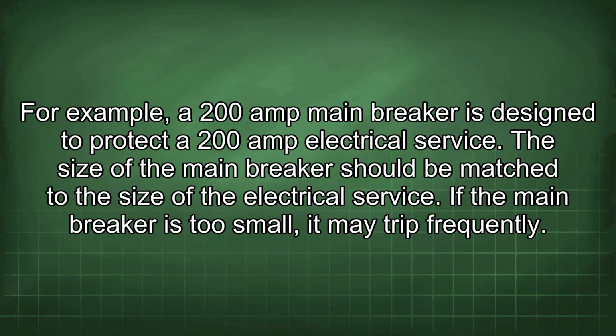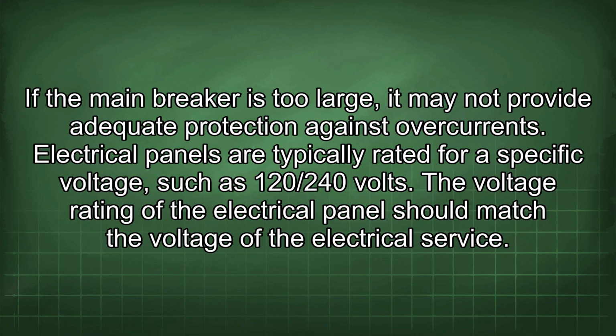If the main breaker is too small, it may trip frequently. If the main breaker is too large, it may not provide adequate protection against overcurrents. Electrical panels are typically rated for a specific voltage, such as 120/240 volts. The voltage rating of the electrical panel should match the voltage of the electrical service.